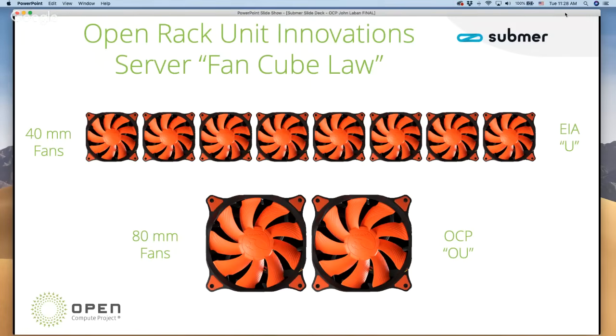There's something you probably learned at school, the fan cube law. I learned it when I was 16, doing physics. The fan cube law says: if you reduce the speed of the fan by 50%, you reduce the energy to spin that fan by 7/8. So comparing the top row configuration with the 2 fans at the bottom, those bottom fans will use nearly 90% less energy to push air through the server than the fans at the top.